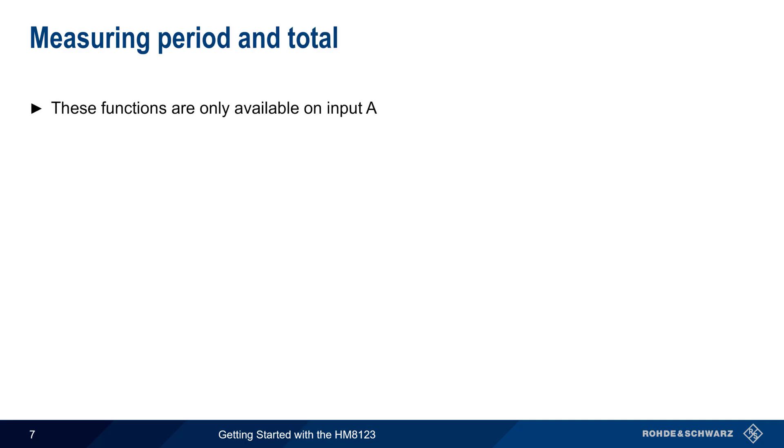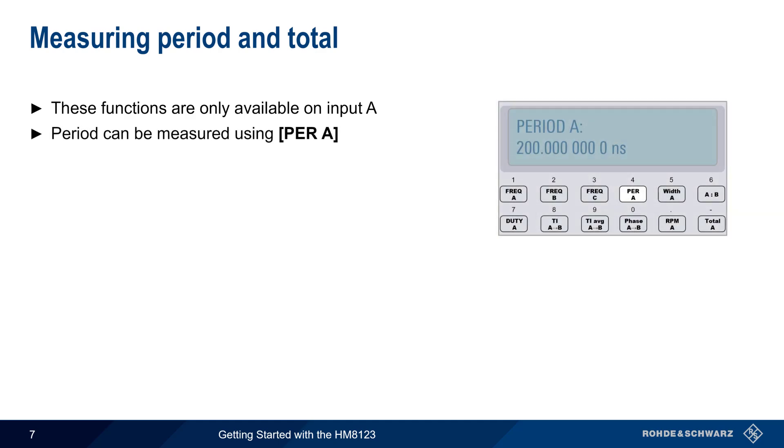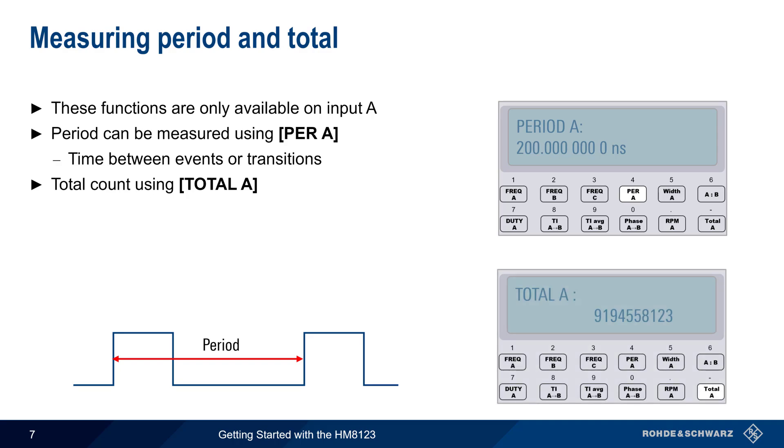The period and total functions are only available on input A. Period can be measured by pressing the period A button. This is the time between events or transitions. The total A key begins a count of all events seen. This can be reset by pressing total again, using the reset button, or by means of a signal at the reset BNC connector on the rear panel.